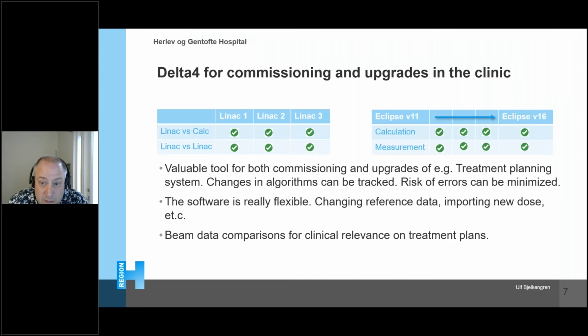So for that we used the Delta 4 system. We calculated plans on the Varian golden beam data, and we calculated plans on our own beam data, comparing relevant treatment plans in the Delta 4 software, and our conclusion was that our own beam data was superior to the Varian golden beam data, so we actually stuck with our own data and rejected the golden beam data. So that is one idea what you can use the Delta 4 software for.